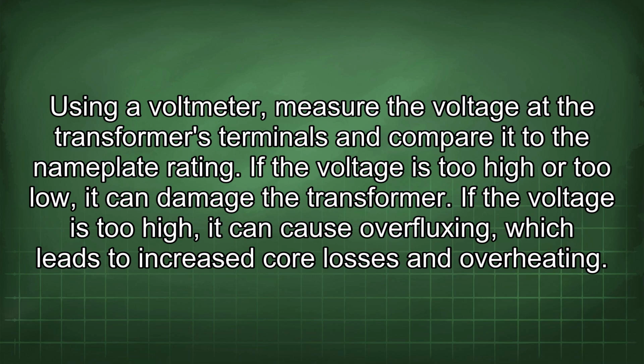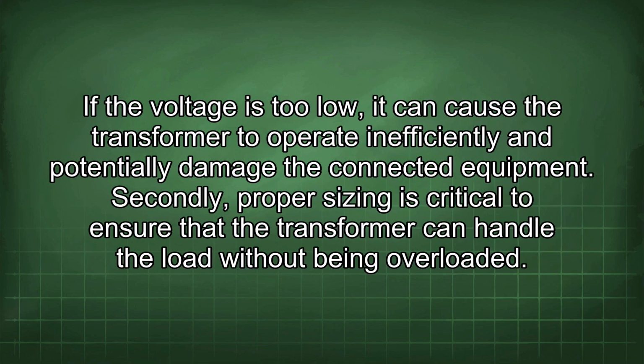If the voltage is too high, it can cause overfluxing, which leads to increased core losses and overheating. If the voltage is too low, it can cause the transformer to operate inefficiently and potentially damage the connected equipment. Secondly, proper sizing is critical to ensure that the transformer can handle the load without being overloaded.